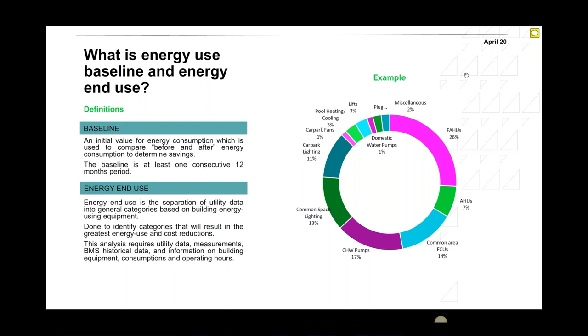So these are the things that you need to look at. I would really not look into the lifts. It's not going to save much. Even if I save 50% of the lifts' energy consumption, it's not going to end up with a lot of savings. So I would focus on the lighting, the chilled water pumps, the ventilation as well.